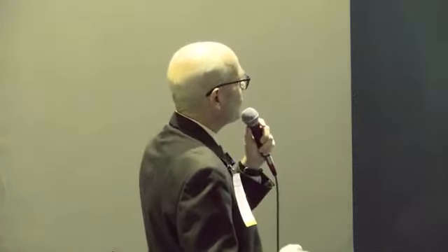This is from West Union. Remember how I said they did this at the same time as the water lines? You can see a new water line coming into this, which they had to run to all the buildings downtown. Then they have two geothermal lines coming off of that, and they just stubbed them into every building, kind of like you would do with natural gas.